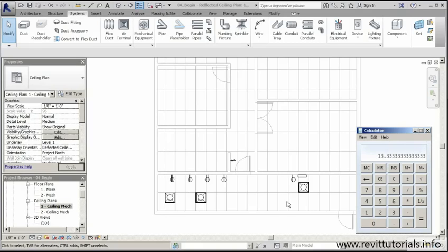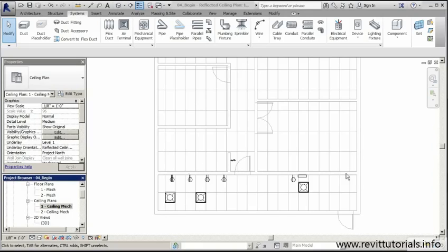I'm going to close this out really quick, and we can start placing our outlets here. When I place my outlet, I'm going to want the first one here to be GFCI protected, and all the ones following that on that circuit will also be protected. So I really only need to have one GFCI protected. If I wanted to, I can have each individual one, but that's a little bit overkill. Having one in place is just enough. Once that trips, everything else in that circuit will trip as well. So it's a real simple, basic approach to getting it done.